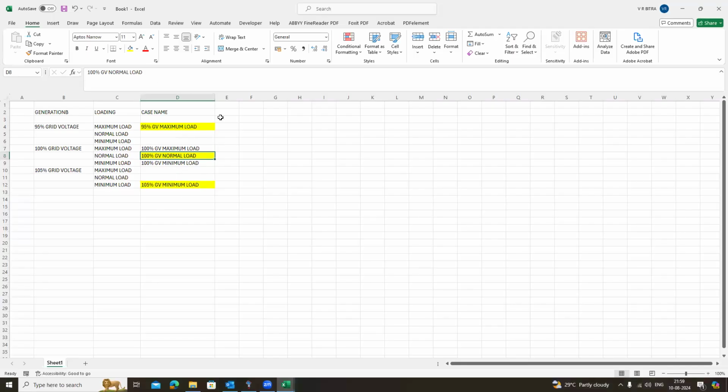But in a year, you have 365 days, 24/7, and the total will be 8760 hours. So an extreme will be there maybe for a few minutes in an operation. Predominantly the operating point is going to be in between. So if the customer asks, we have to perform all the 9 cases. If the customer doesn't ask anything, probably performing case 1 and case 9 will be sufficient. That's enough.